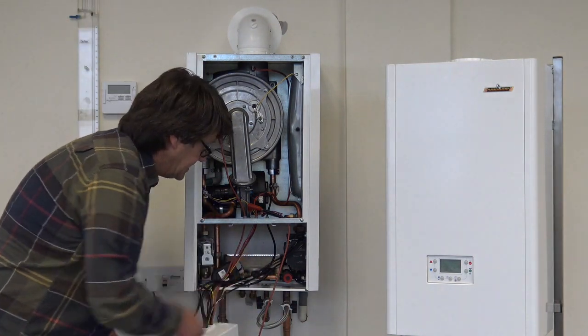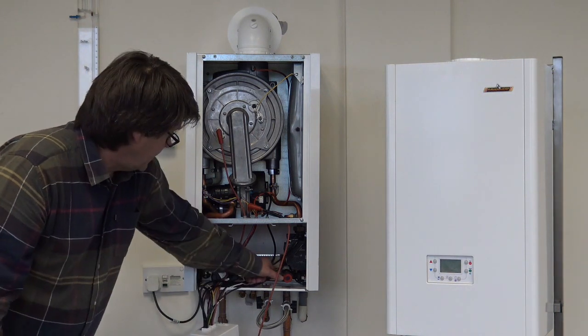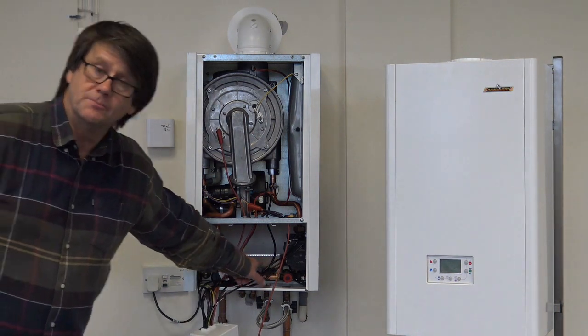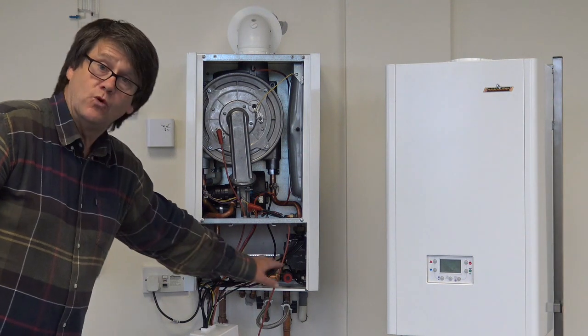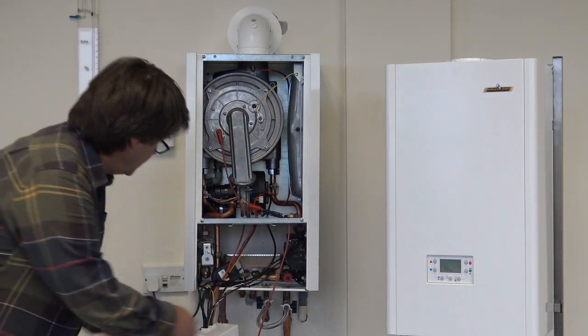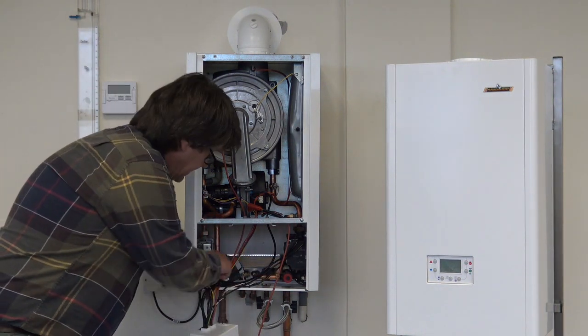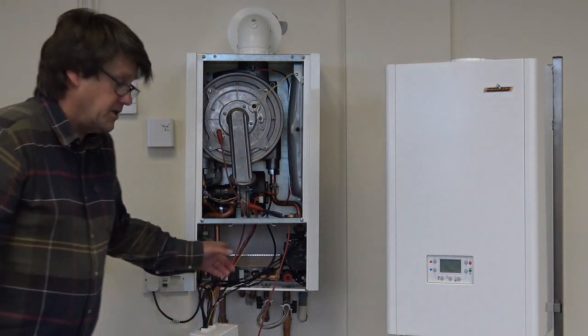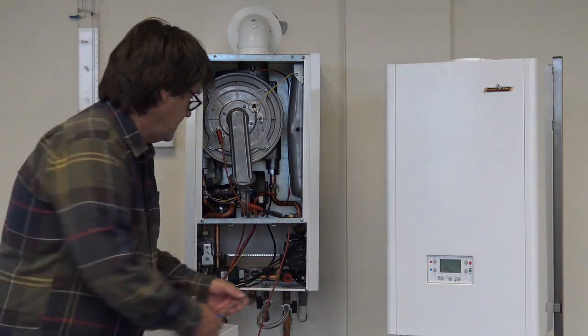So, the plate heat exchanger - take the bottom plate off with an Allen key, it's got to be one of the easiest, guys. You can work on this sat in an armchair. Gas valve to the left hand side, and then your motor on your diverter valve. It's a dream.